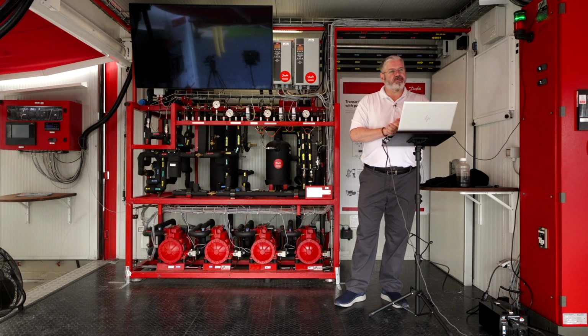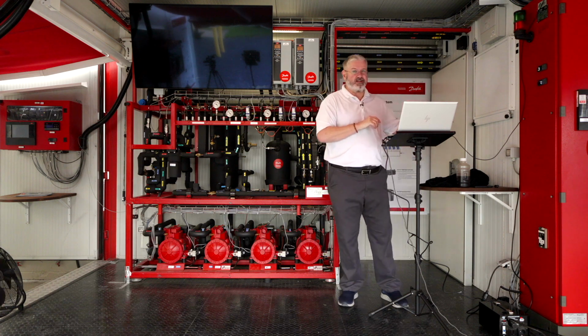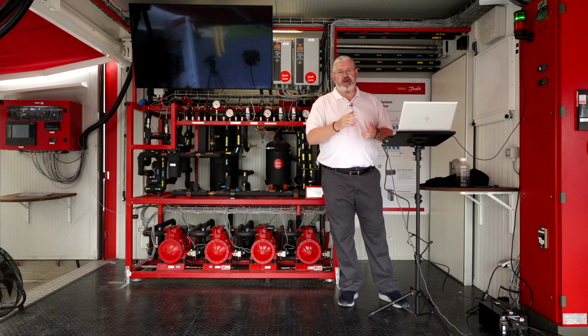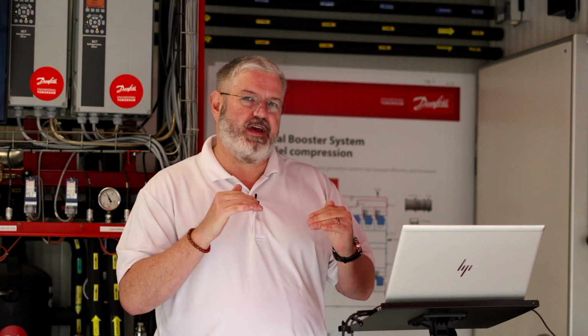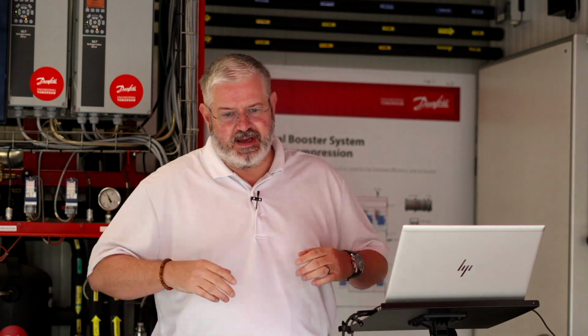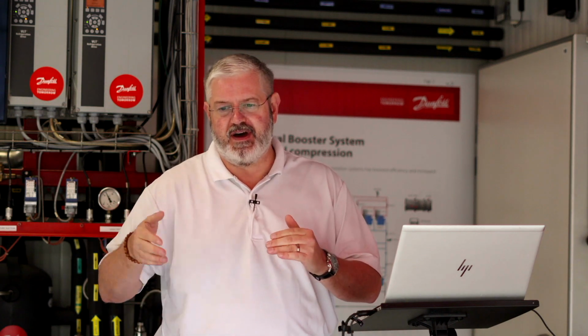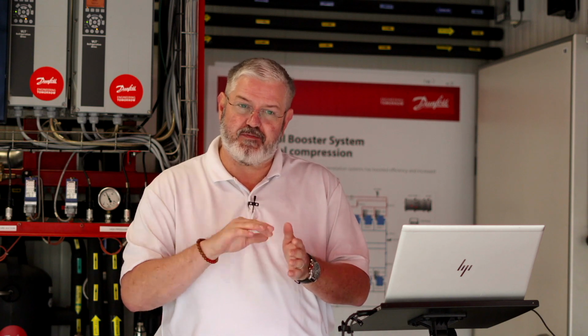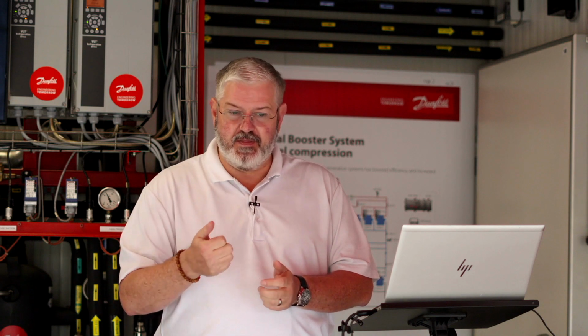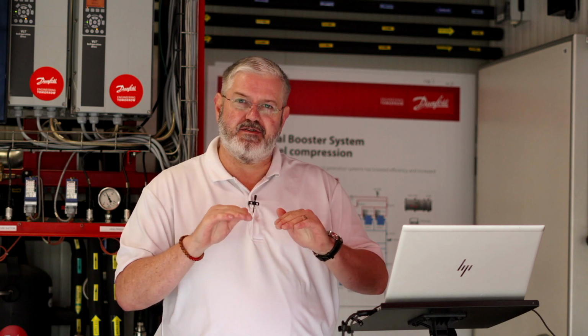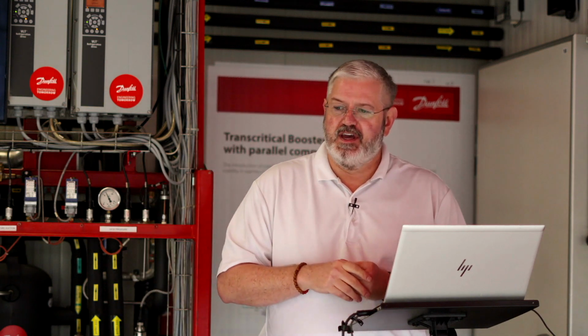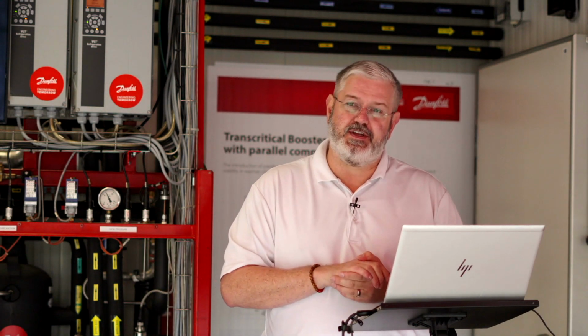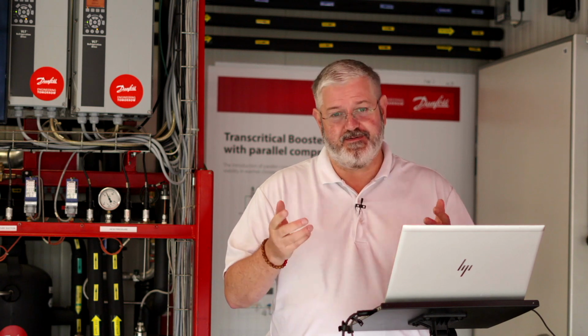When will we see mass adoption of the Danfoss mechanical TXV for CO2? It's available. I have one in a box inside this walk-in cooler. We already have the mechanical TXV. I personally struggle to see where that would be used, other than maybe a C-store application, box by box. And I'm assuming a small condensing unit with CO2 is still going to have some type of high pressure valve to give us liquid, but also to maintain a limited amount of pressure on the TXV. But the mechanical TXV for CO2 exists today and is available. It is brought to you by Danfoss.